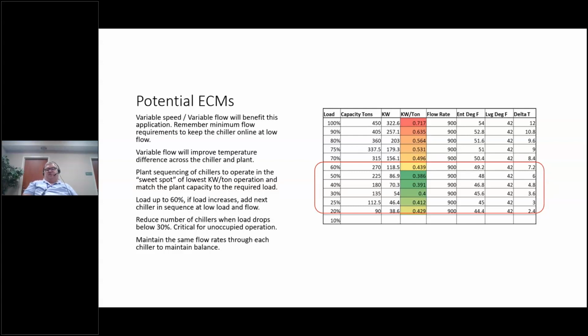Maintain the same flow rates through each chiller to keep balance. That's where variable speed comes in. You'll probably need something to tell you what the flow is, like a flow meter or pressure differential, and do the calculation, so you can decide and vary the speed automatically through each machine. Instead of 900 gallons per minute through one machine, you'd have 450 gallons through two at the same time, which makes it operate at the most efficient point. Try to maintain that balance.